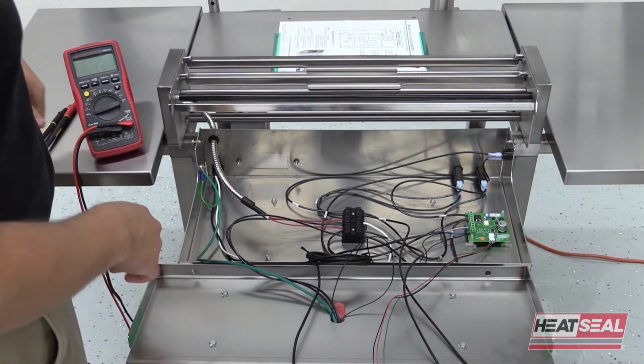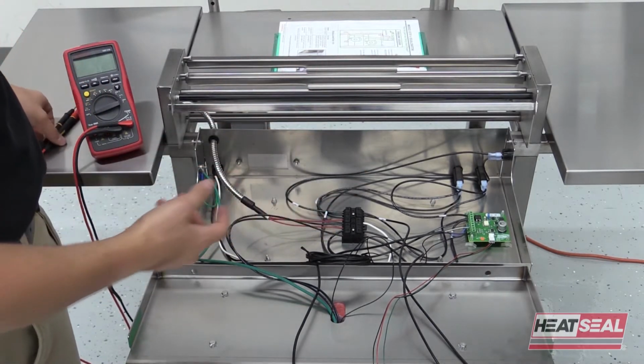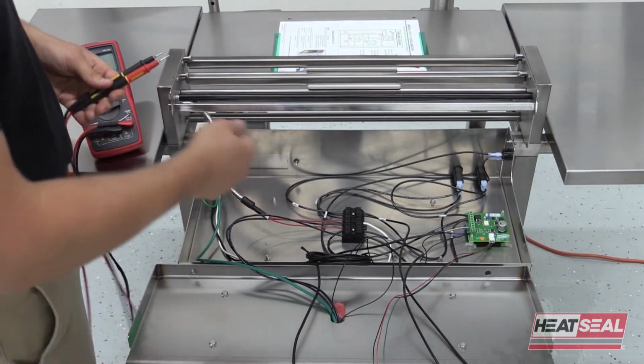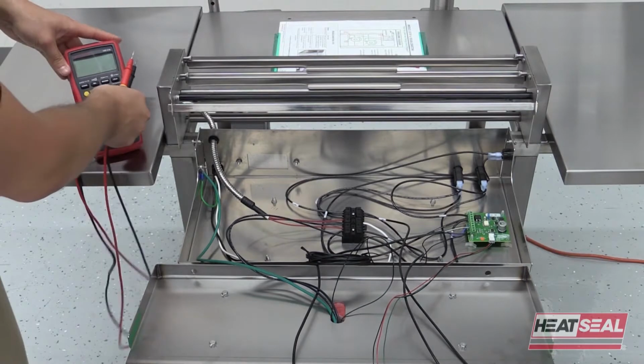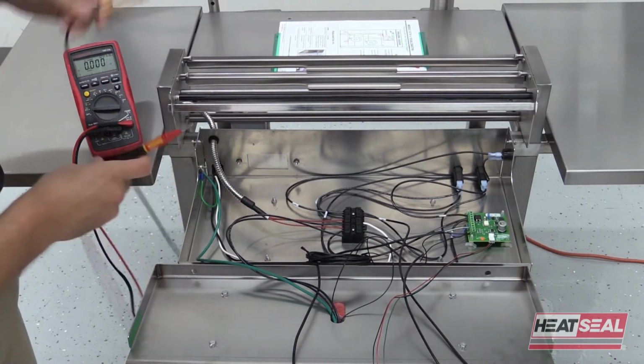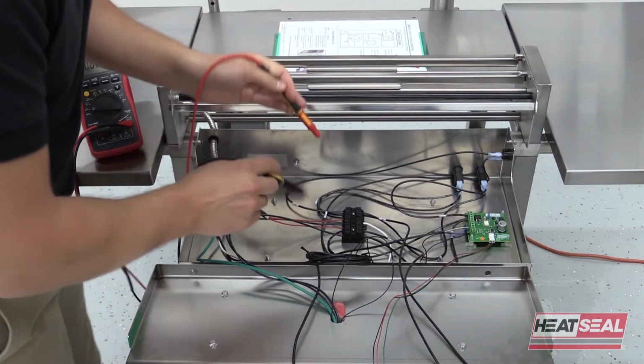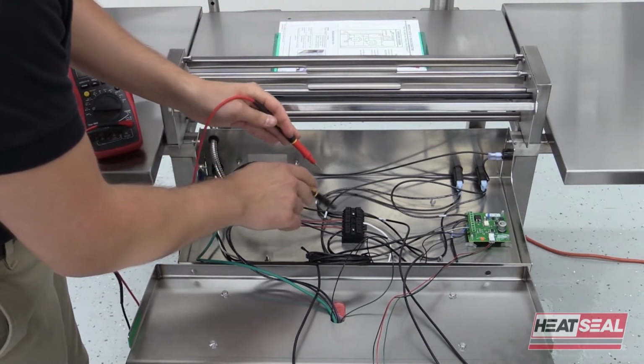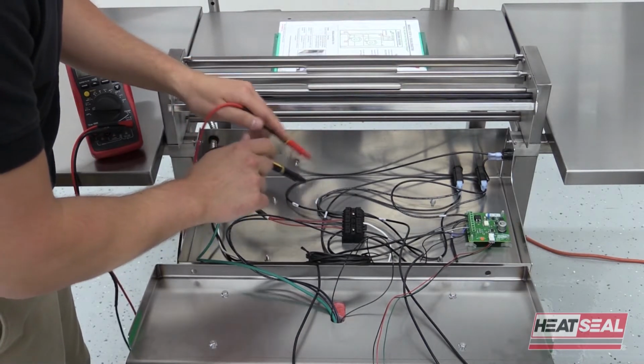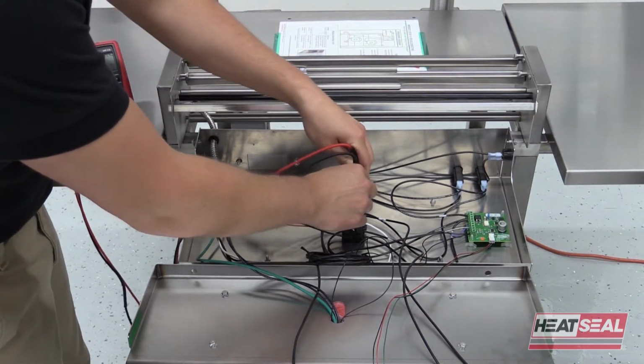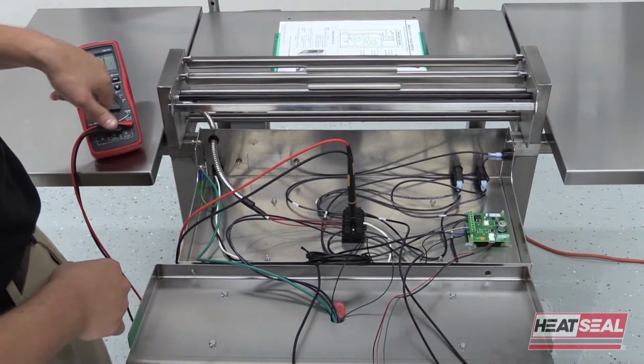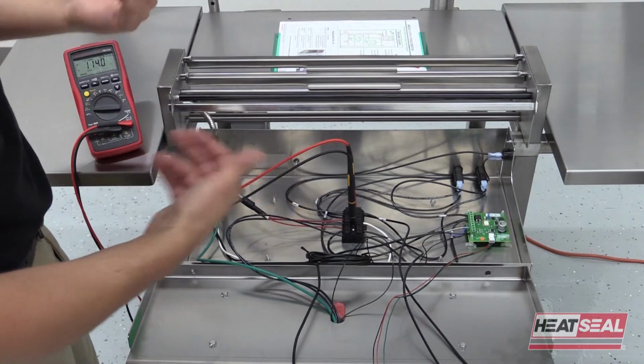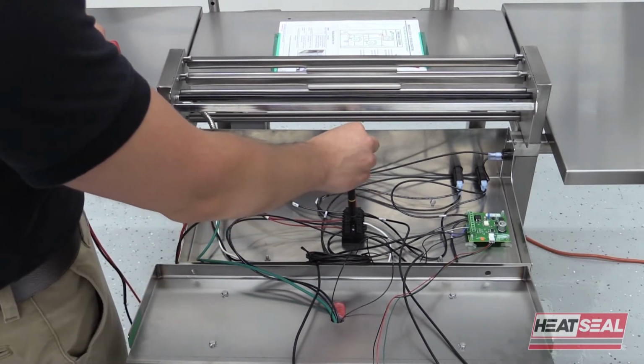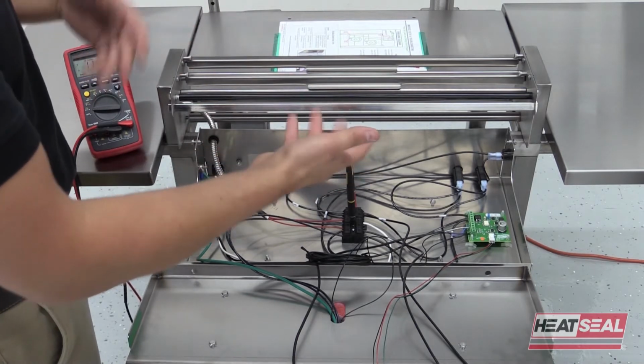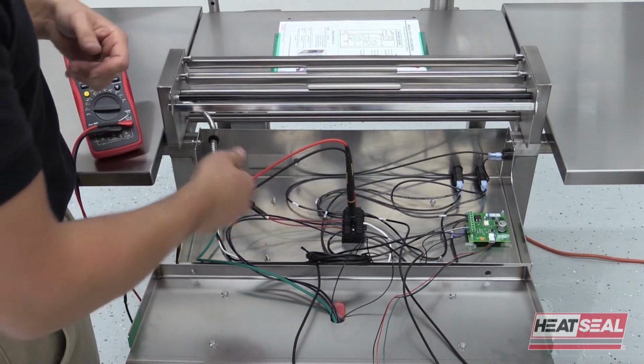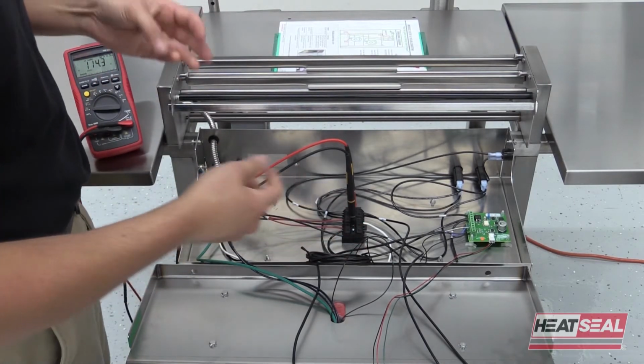Okay, so if your hot rod checks out okay, but you're still having issues with the hot rod heating up, and the 1 amp circuit breaker doesn't show as tripped, what you can do is plug the machine back in and turn it on. We're going to switch our multimeter to read AC volts, and there are a couple of small holes on the top so you can insert your meter probes. So we'll stick the probe in there to see if we get the 110, 120 volts. At that point, if you don't have voltage there, the issue could still be the circuit breaker. I would replace that, and if that's not the case, then you may have a problem with the GFI.